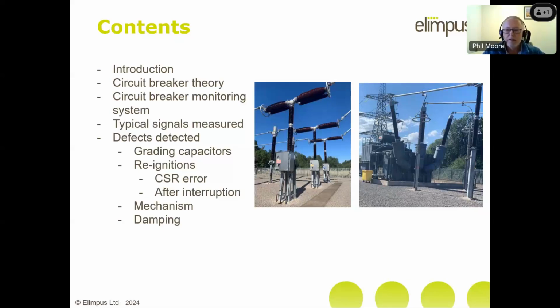And if you were looking for a sort of tutorial on general circuit breaker monitoring, you might be a little bit disappointed, because I'm really talking about something very, very specific to shunt reactors, which are quite a difficult application for circuit breakers. I'll show you some of the typical signals we've got, and I'm going to show you a lot of the defects that were discovered by this approach. This has all been done in cooperation with National Grid, and it's really been very, very successful. And I think you'll find when I show you some of the results that it's produced advance warning of issues that otherwise would have pretty much gone unnoticed.